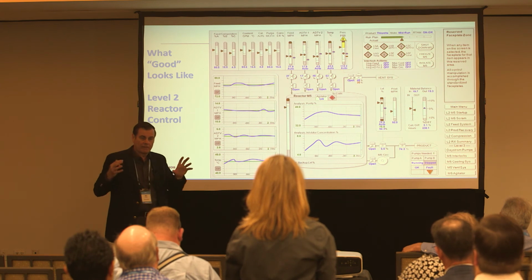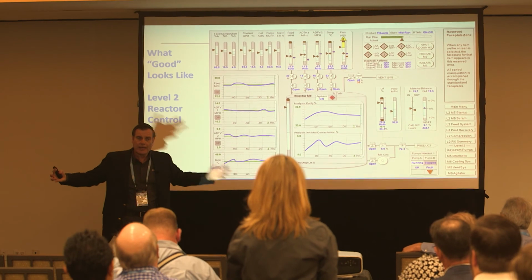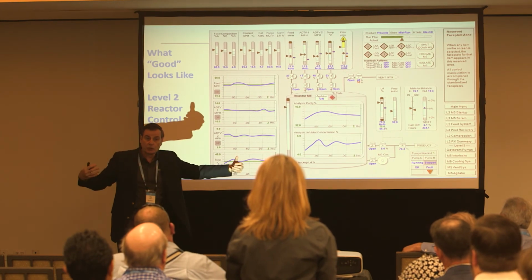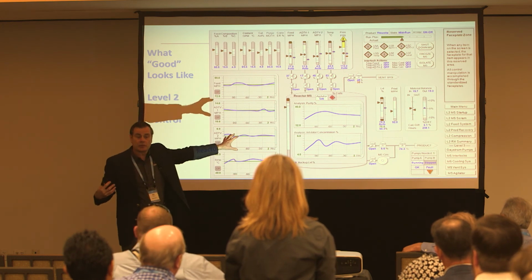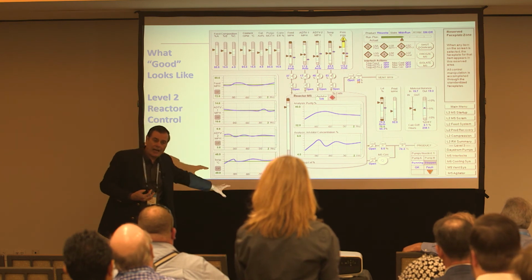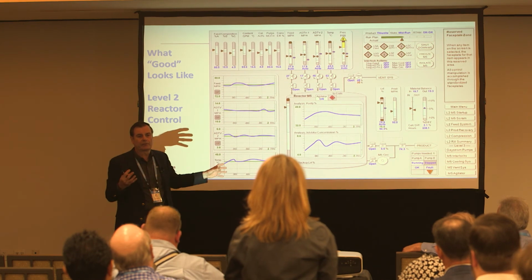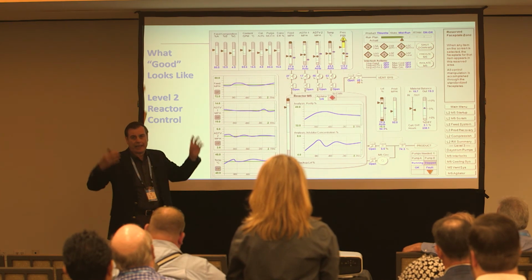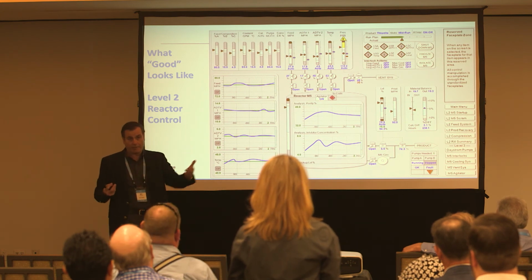One of the things we say is, don't say to your operators, we're going to get rid of your graphics and give you all new ones. Don't do that. Keep everything you have, add some properly designed level 1 and level 2s, and they will start using them because they're better. And we have case studies to prove this. Over time, you can make your level 3s better, but you don't have to throw everything away. You don't even really have to revise it. And don't give me this stuff, oh, my operators will be horribly confused. Well, your operators have a PC and an iPad. They can go from one to the other. Don't be patronizing to your operators.